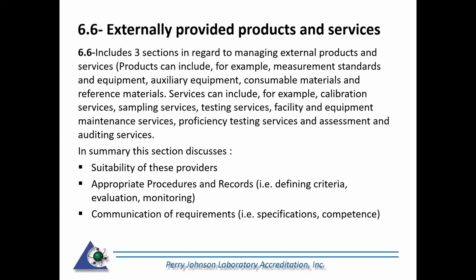Okay, so I want to move on to 6.6, and this is what I was just referring to when we were talking about traceability and the use of your service providers, for example, calibrators. If you're used to 17025-2005, this section is new in some ways, where they got rid of subcontractors and combined all this into one. But they do give you a definition in the standard itself of what we'll be talking about: externally provided products and services. Products can include measurement standards and equipment, consumable materials and reference materials. Services can include calibration services, sampling, proficiency testing services, and assessment and auditing services.